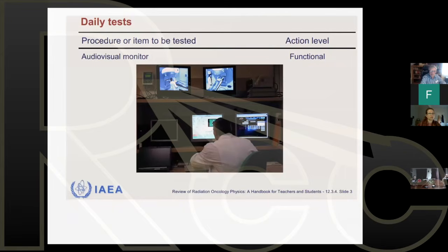But the first test that I had mentioned was audiovisual monitoring. Very important. You have to be able to see the patient and hear the patient. Most centers like to use two cameras. Not only do you see the patient from a different angle, but if one camera breaks, you always have the backup camera, the second camera working, so you do not have to cancel treatments that day if a camera is malfunctioning.